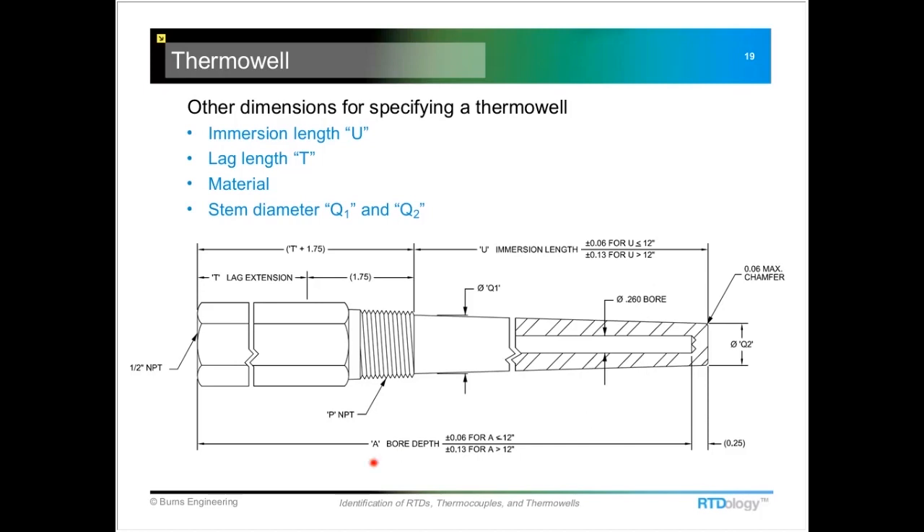You want to make sure you get the same thermowell so that you have the same performance as the original. The other dimension is the lag extension, usually indicated by the letter T, and the instrument connection thread — most of these are a half-inch NPT, though if it's metric it might be an M20 size.